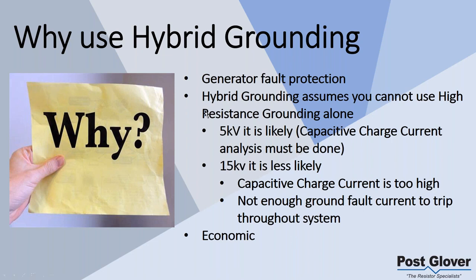So that's the point. If you were to look at your 5 kV system and you want to apply hybrid, I would recommend you first figure out if you could use high resistance ground by itself. And for that to happen, you need to do a capacitive charge current analysis. We're not going to go into detail on what that is; we've done it in previous presentations. Basically, it's the amount of current that your system's capacitance produces on a ground fault, and it competes with the high resistance ground system. The bottom line is you don't want to overvoltage your system, so you want to make sure that's low enough to use high resistance ground. Once again, if you have a question about that, feel free to ask. We'll take it, but we've also addressed that before in a previous presentation.